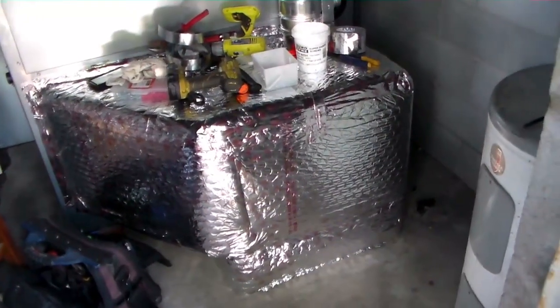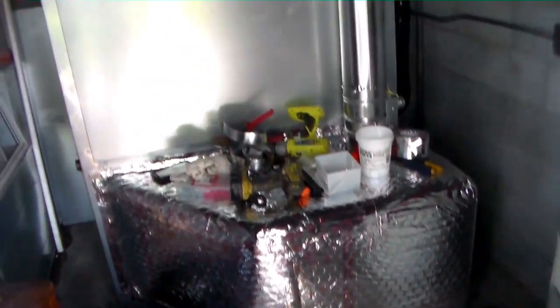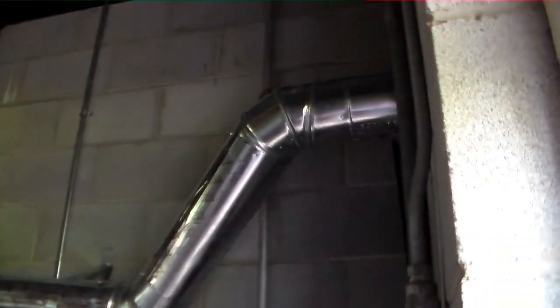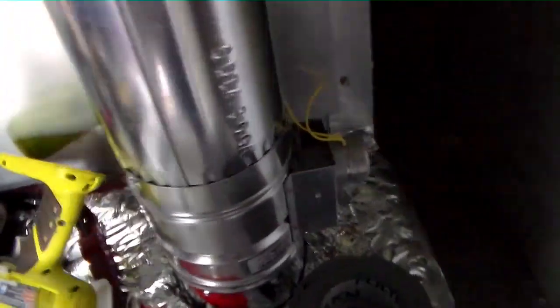Guys, I finished building my box and wrapping it. I have my outside air duct run across over here, so I had to seal it up. Comes out to our cap here with the screen built into it. Low voltage is coming along. This is a power open, spring closed, fresh air damper. Some of our low voltage is finished. We changed our motor over to 230 3-phase because they come shipped for 460.